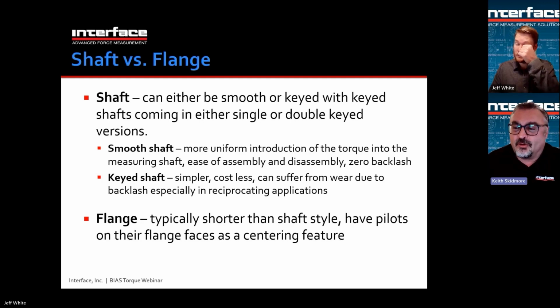And the shafts can either be smooth or keyed, and keyed shafts can either have single or double keyed versions. And then in Europe, typically the keyways are well defined per a DIN 6885 spec. But keys are okay, but we do prefer smooth shafts, and most of the torque sensors that we sell with shafts are smooth shafts. So with a smooth shaft, you have a more uniform introduction of the torque into the measuring shaft, because the couplings actually grip the shaft all the way around its perimeter instead of engaging a key. And then also those types of gripping couplings can come apart easily. You can unscrew or loosen the bolts and it'll come back apart.